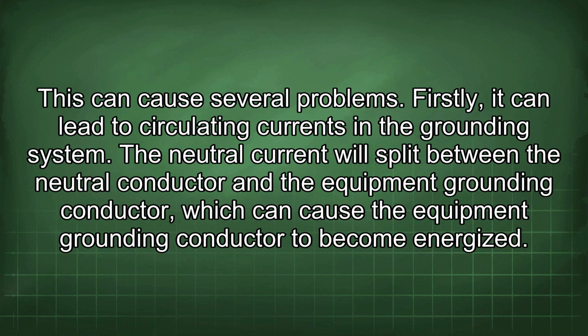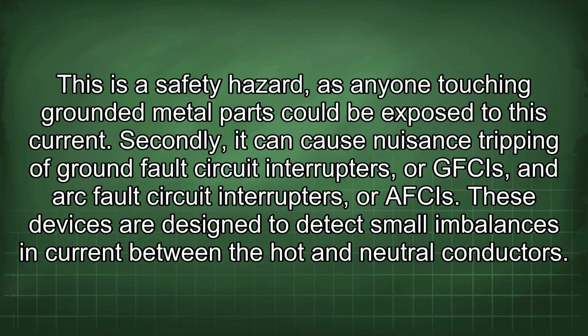This can cause several problems. Firstly, it can lead to circulating currents in the grounding system. The neutral current will split between the neutral conductor and the equipment grounding conductor, which can cause the equipment grounding conductor to become energized. This is a safety hazard, as anyone touching grounded metal parts could be exposed to this current.